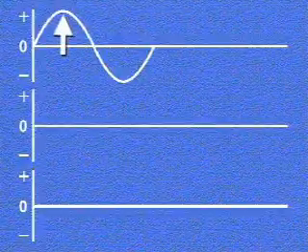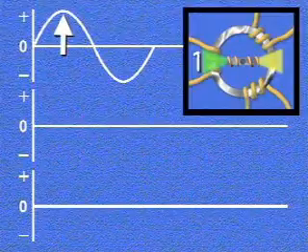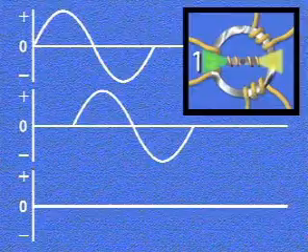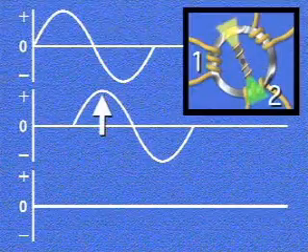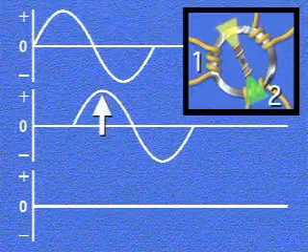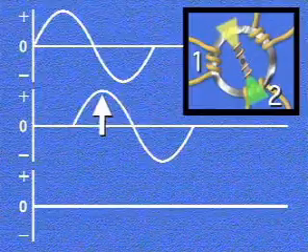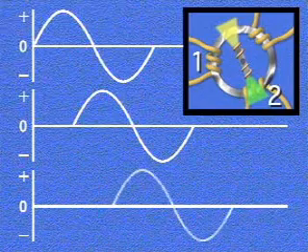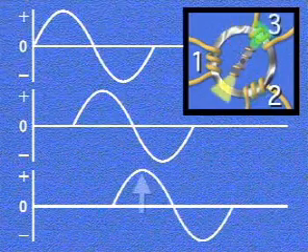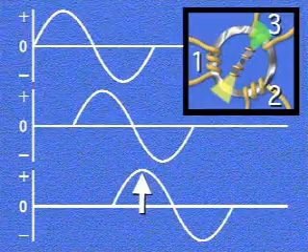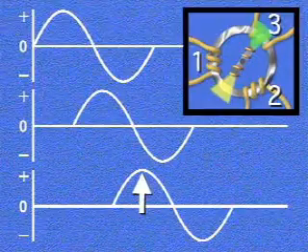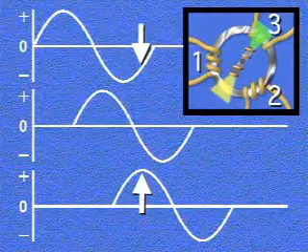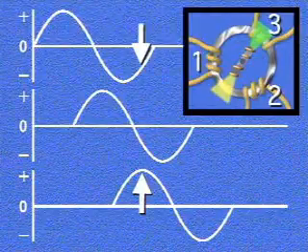Maximum positive voltage occurs as the field around the north pole of the electromagnet crosses the first stator winding. Maximum voltage in the second phase occurs as the field crosses the second winding. At this point, the first phase voltage is decreasing. In the third phase, maximum voltage occurs as the field around the north pole crosses the third stator winding. Now the south pole's magnetic field has crossed the first winding, inducing a negative voltage.